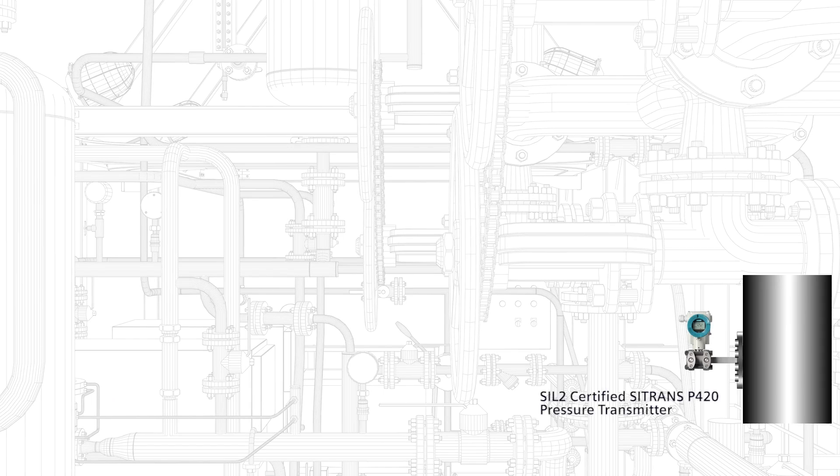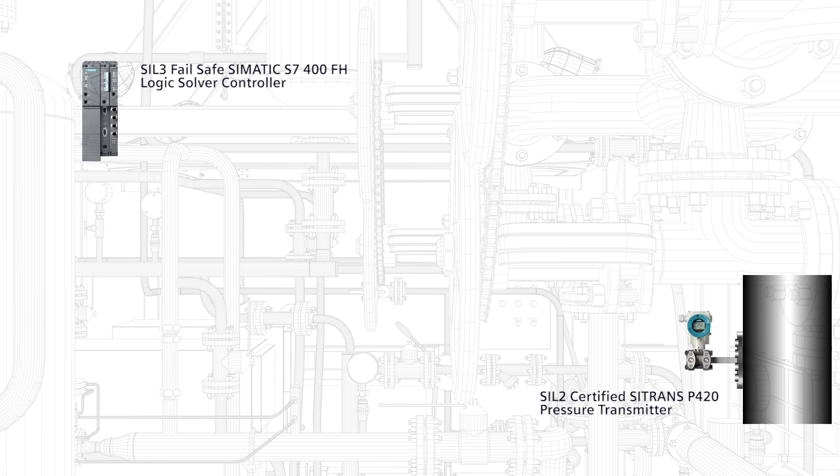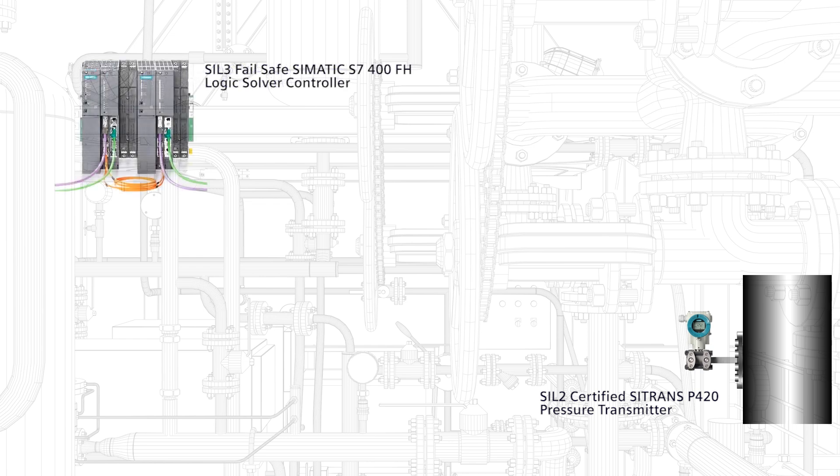Let's see an example. Let's say we have a safety instrumented function for pressure, and we have selected a field device which is a SIL2 certified SITRANS pressure transmitter P420. Then, in this safety instrumented function, the signals from the safety transmitter have to be processed by a safety controller — a controller with a high safety integrity level and high safety performance.